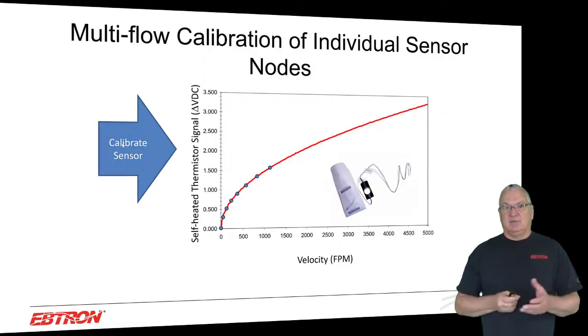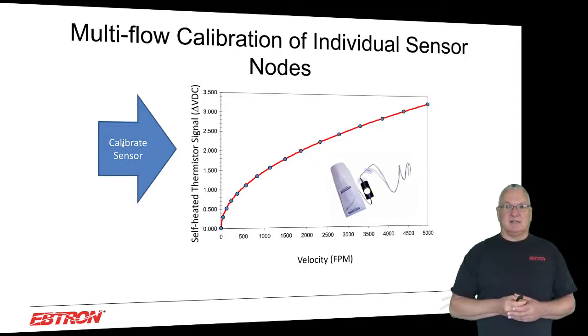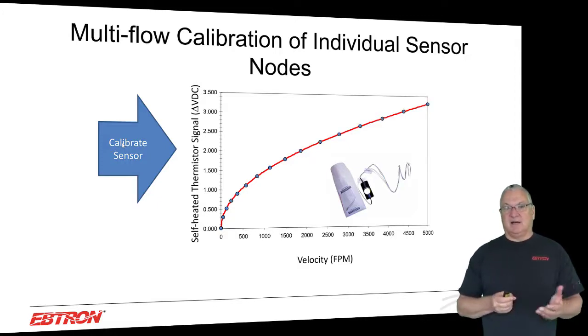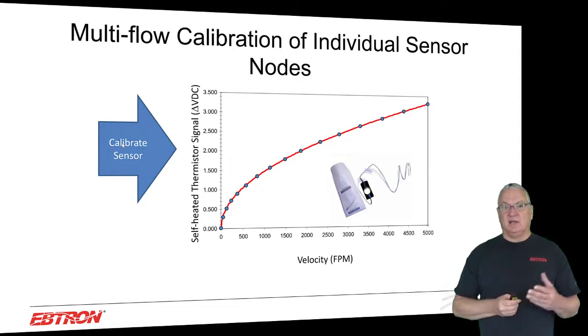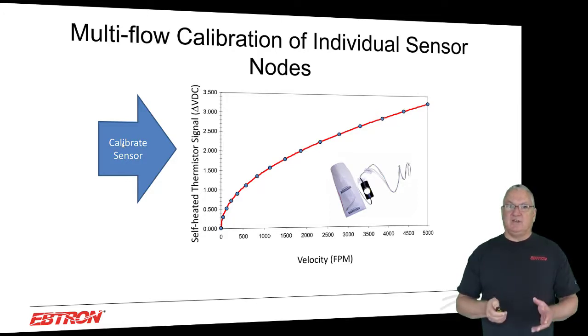Okay, and this would be typical for a Gold Series ducted probe where we'll calibrate at 15 airflow rates between 0 and 5,000 feet per minute plus still air, so 16 points. All right, it's a very unique process. Think about that. If you have one of our EBTRON products with 16 sensor nodes in it, we've done 16 individual calibrations of those sensor nodes.